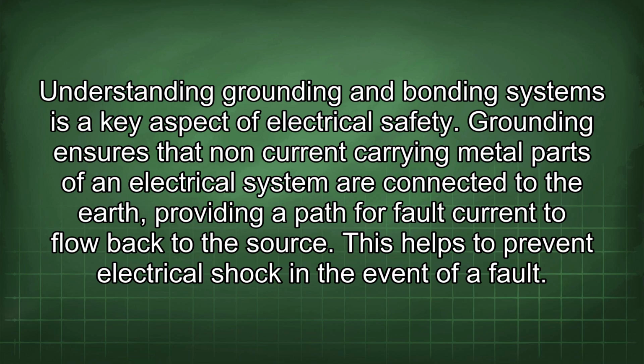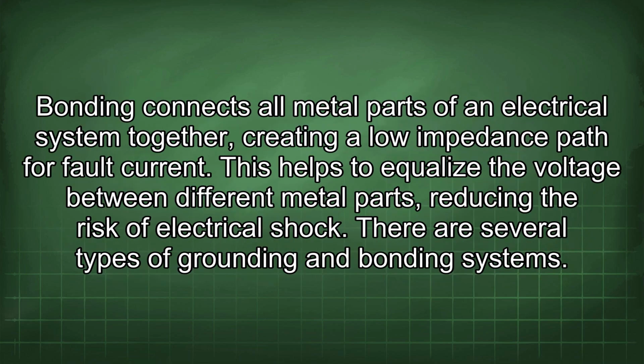Grounding ensures that non-current carrying metal parts of an electrical system are connected to the earth, providing a path for fault current to flow back to the source. This helps to prevent electrical shock in the event of a fault. Bonding connects all metal parts of an electrical system together, creating a low impedance path for fault current. This helps to equalize the voltage between different metal parts, reducing the risk of electrical shock.